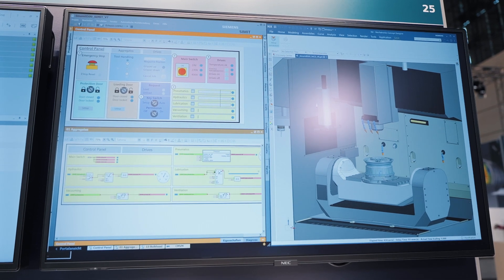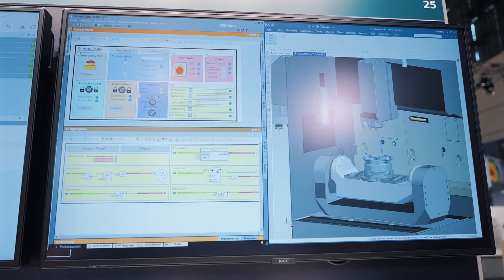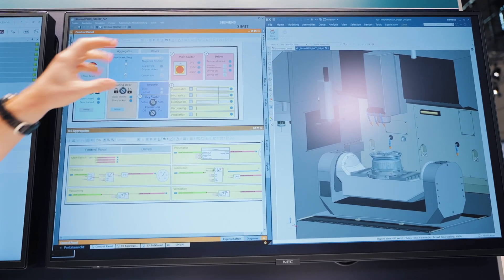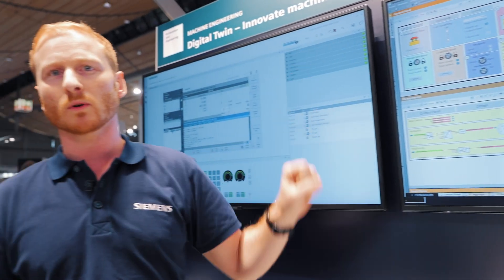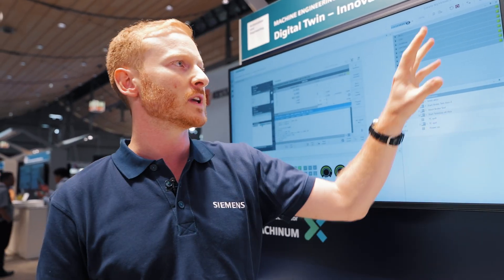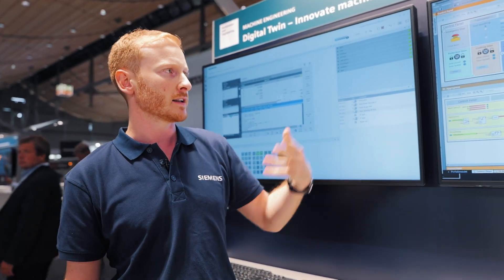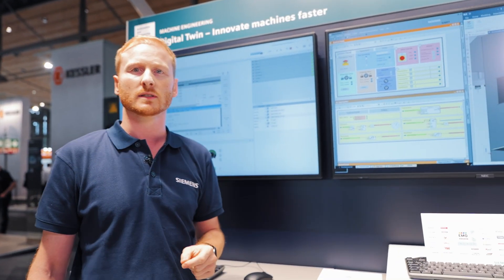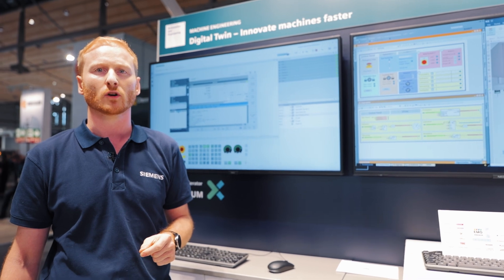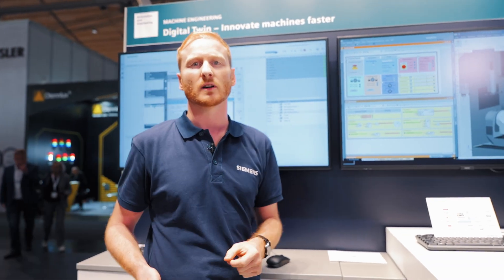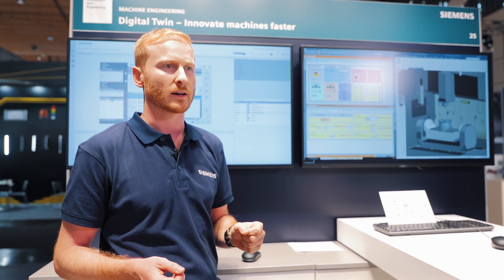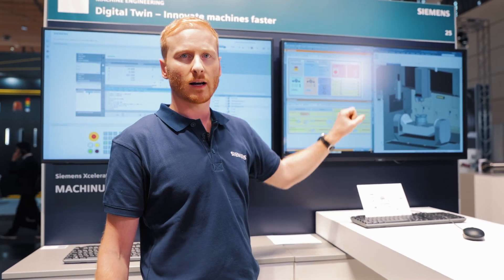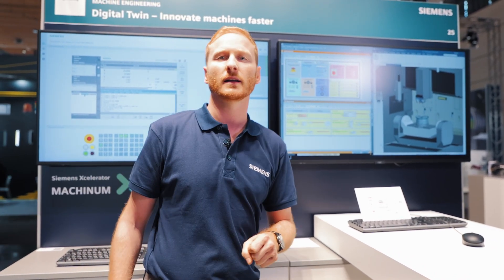In addition, we can interact with our control model via switches. That means the developer has the ability to test the commissioning process, test emergencies, and perform certain aggregate failures. They can test whether the right signals are issued at the right time, and move all the work they would otherwise carry out on the shop floor to the office environment.